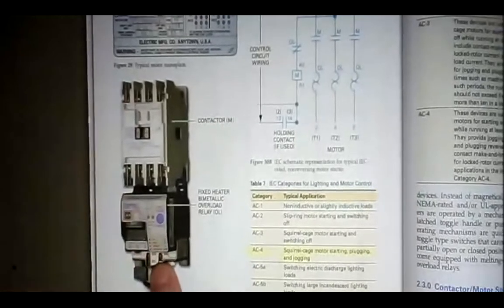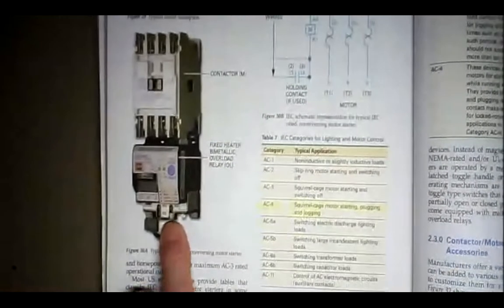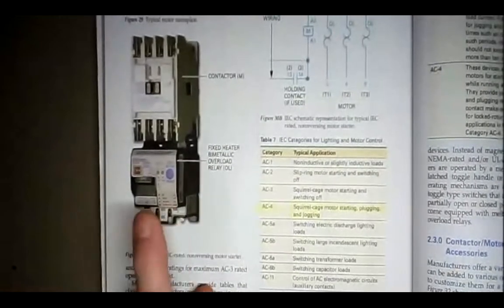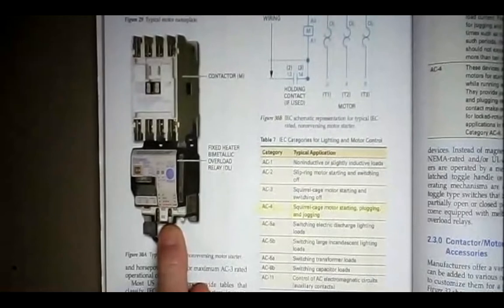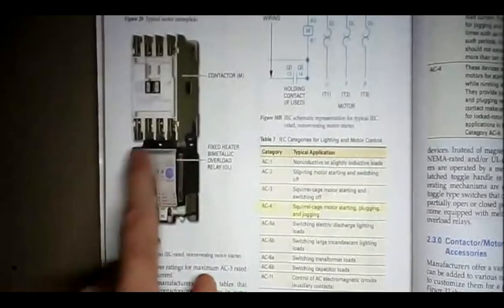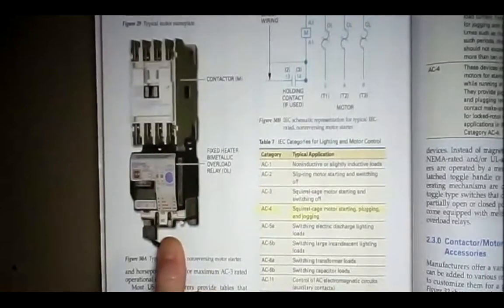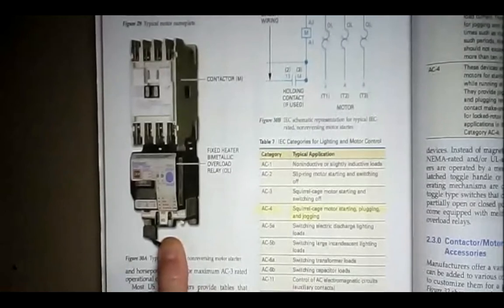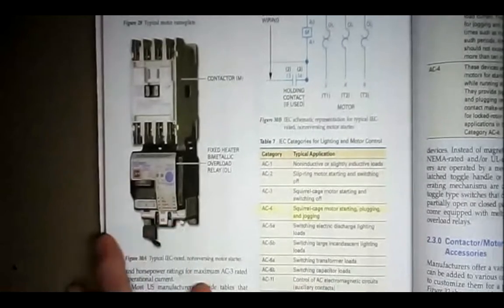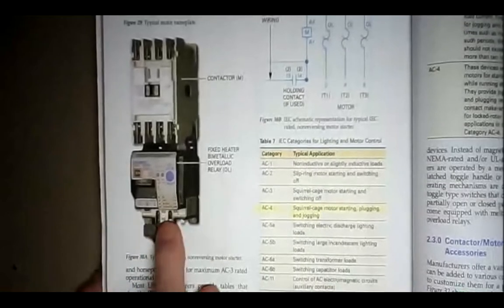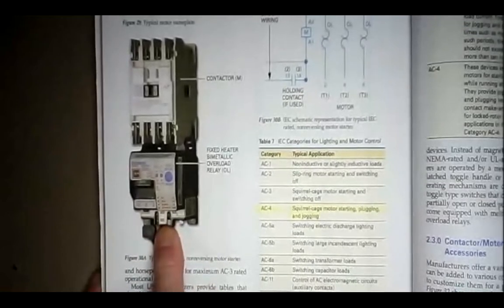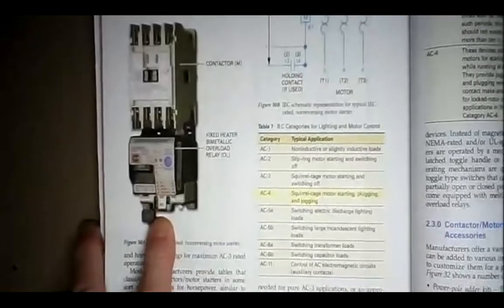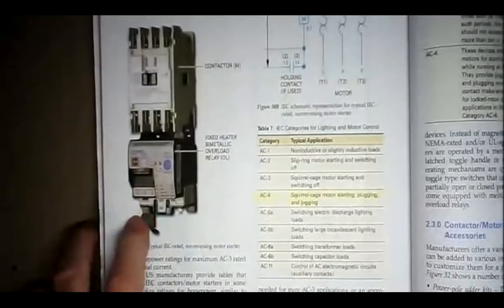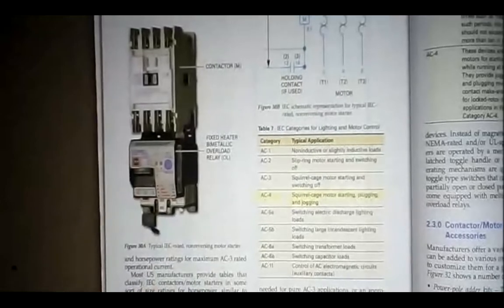Again, the overloads are sealed. It's a complete unit. It's a block. And if the heaters go bad, or if you need to change the heater size for any reason because you're changing the size of the motor, you have to change out the whole overload block. If the overload block isn't bad, you don't have to throw it away. You can take it out, store it somewhere, and you can put a new one in to adjust for that new motor. But they do have to be changed. The entire block has to be changed out. You can't get inside here. You can't change out just the heaters.